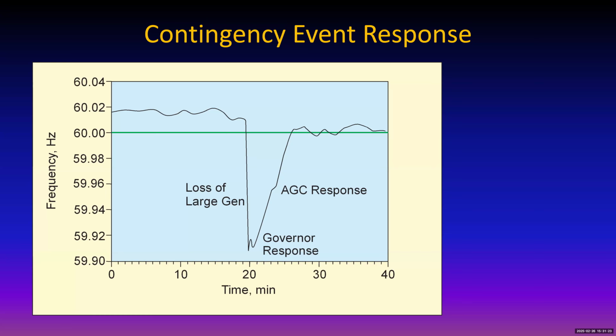This is a typical contingency response — within 6 minutes they're back up to frequency. The grid never did shut down, because it only dropped by 1/10 of a hertz, but that 1/10 of a hertz is enough to get other pieces of equipment's attention, so they turn on and make up for it. And as I was saying, the flywheel is a very helpful piece of equipment for getting rid of these glitches.